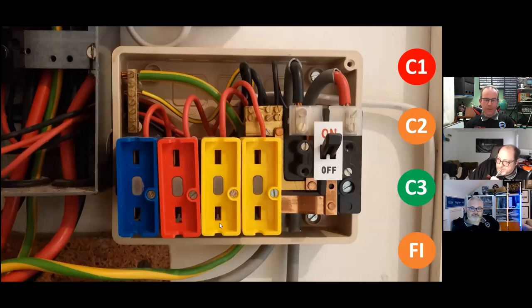I want to know a couple of things. I want to know the prospective fault current. I want to know the use, to see if the end users one day will rip the heaters out and maybe put in sockets. As you say, you're saying about life expired. I want to know about the future, because the idea of these is obviously we're going to inspect for the future. If they are just simple heater systems that don't overload, there's little to no signs of thermal stresses.